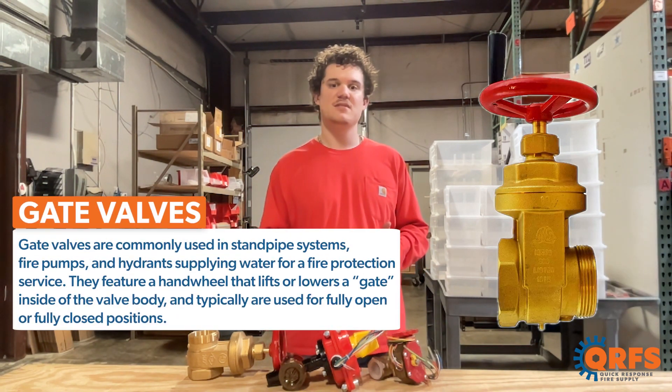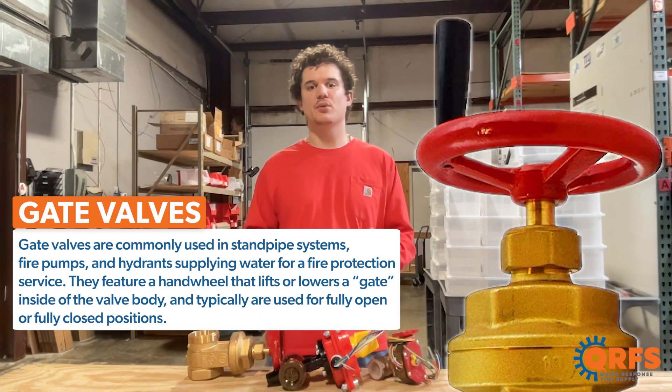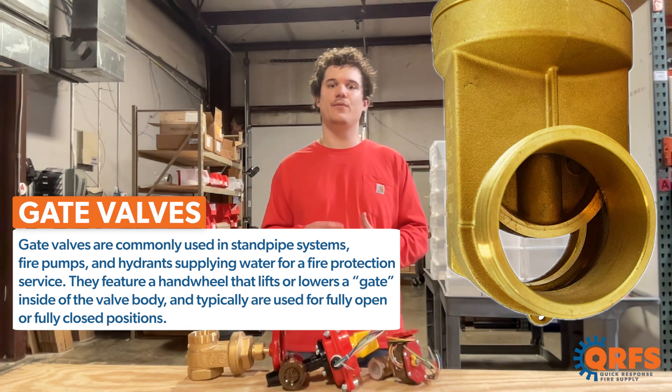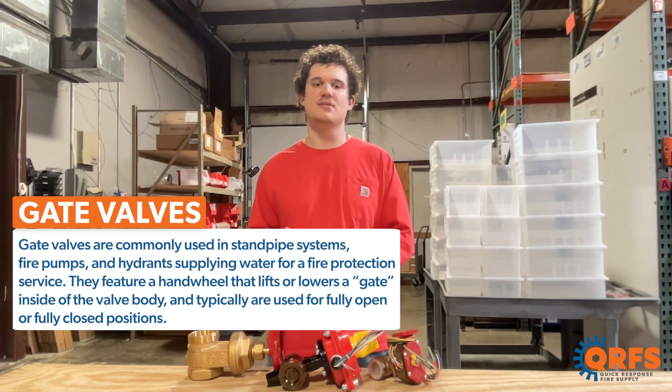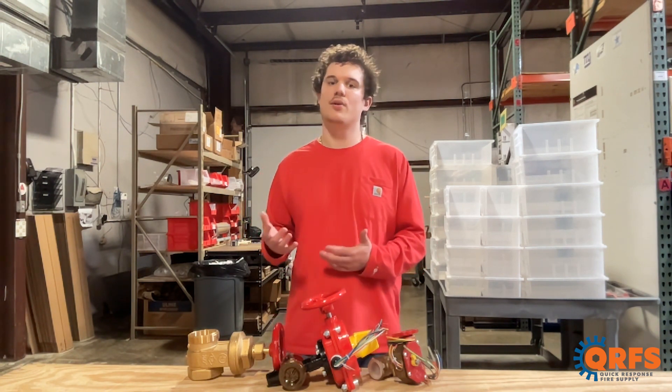Gate valves are commonly used in standpipe systems, fire pumps, and hydrants supplying water for a fire protection service. They feature a hand wheel that lifts or lowers a gate inside the valve body and are typically used for fully open or fully closed positions. They typically feature one NPT and one NST or other hose connection.